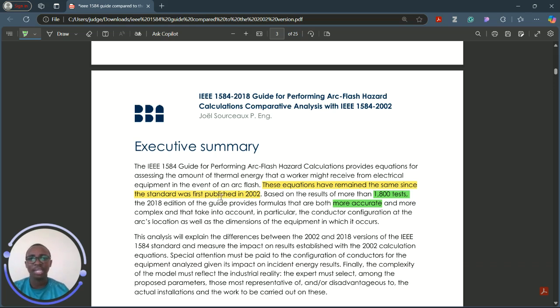So it's safe to say that yes, this is practical, even though we saw that the incident energy levels had decreased from my model. And it's good to note that this still maintains the practicality of the standards in the field, knowing that robust current models were employed to make this conclusion that indeed grounding doesn't have an effect in the calculation of the incident energy.